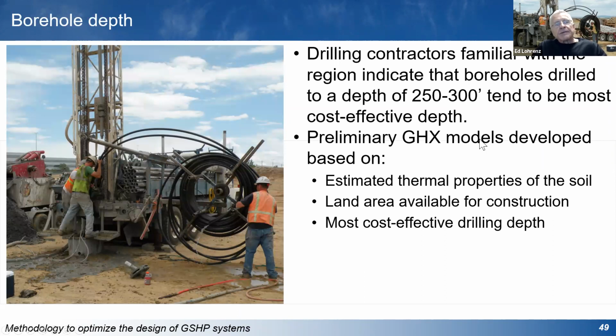The next thing we did was talk to some of the drilling contractors in the region. What's the depth that you would prefer to go to in that region? Are you going to run into problems if you drill beyond 200 feet, or are you going to start running into problems if you go to 400 feet? The consensus, after talking to a couple of drillers in the area, was that about 250 to 300 feet was probably the most cost-effective depth to drill at. So if we've got the land space available, we wouldn't design a ground heat exchanger to go to 400 feet, because the drilling contractors are going to have to charge more for that. So based on the thermal properties, the land area, and the most cost-effective drilling depth, we try and design the ground heat exchanger within those parameters.